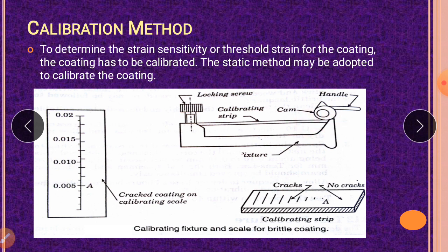The lacquer should be scraped from the calibrating strip at the end which is to be clamped in the loading fixture and the point of contact with the cam. This is the cam where the contact occurs. When clamping the strip in the calibrating fixture, the locking screw should be tightened until the strip just touches the bottom of the loading cam to ensure the consistency of strain between the calibrating fixture and the calibrating scale.